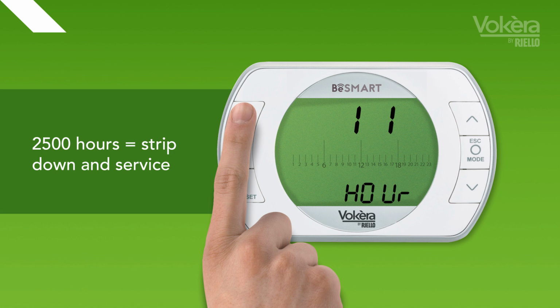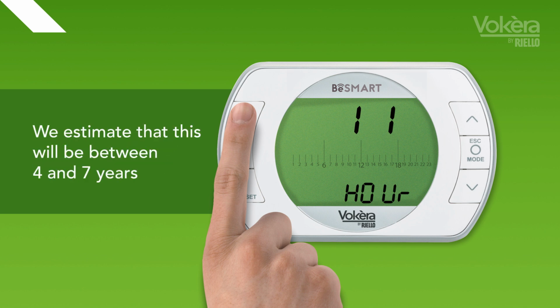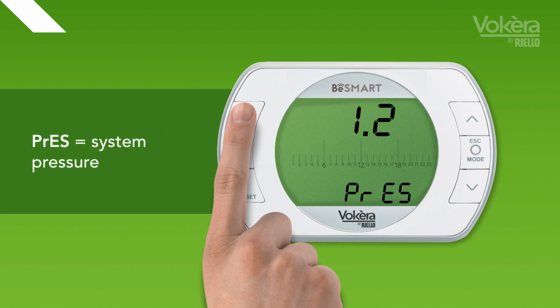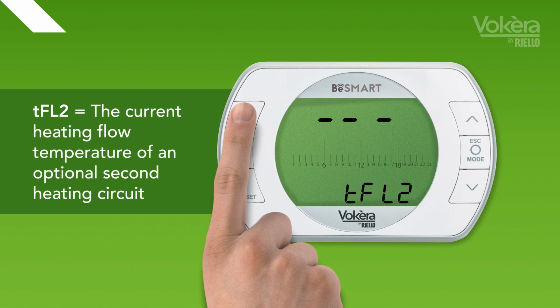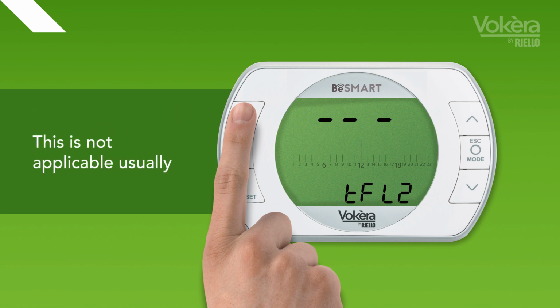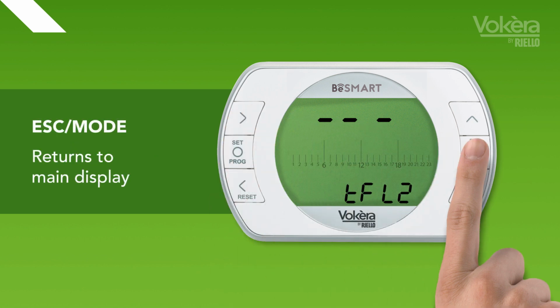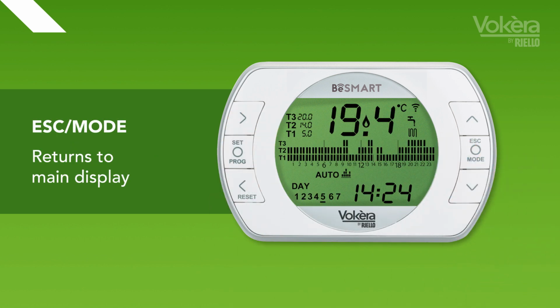2,500 hours equals a strip down and service. We estimate that this will be between 4 and 7 years dependent on boiler operation. PRES may indicate system pressure. TFL2 is the current heating flow temperature of an optional second central heating circuit. This is not applicable usually. Press Escape to return to the main display or the Set button and then Right to adjust the next option.